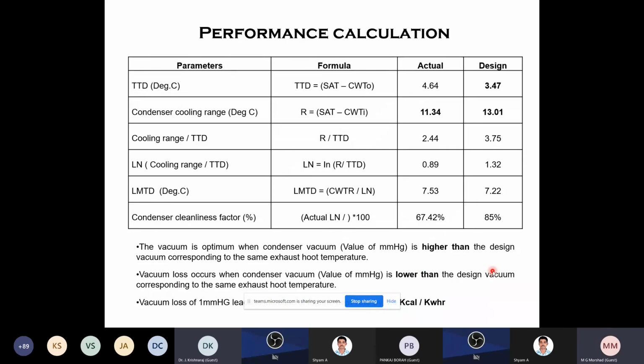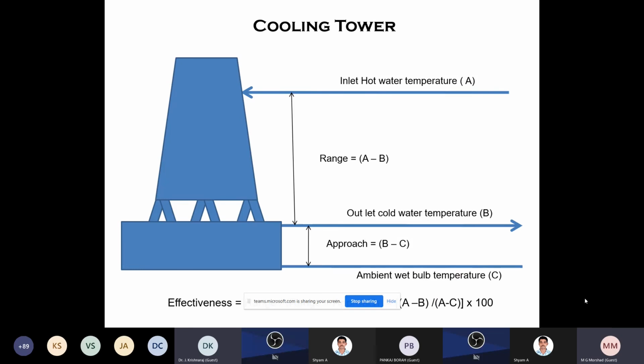So the cleanliness factor is there. Vacuum is optimum when the condenser vacuum is higher than the design vacuum corresponding to the same exhaust hood temperature. Vacuum loss occurs when the condenser vacuum is lower than the design vacuum corresponding to the exhaust hood temperature. So 1 mm loss of vacuum is somewhat 5% loss of something, they have given. Okay, so these are the established facts and established design. Now I am coming to the cooling tower, the natural draft cooling tower.